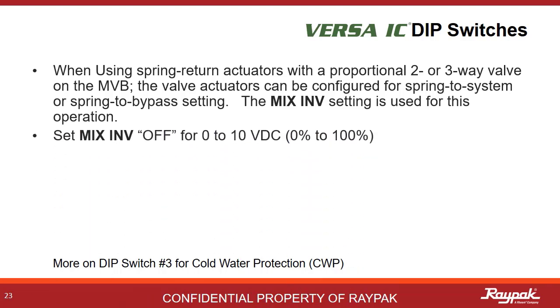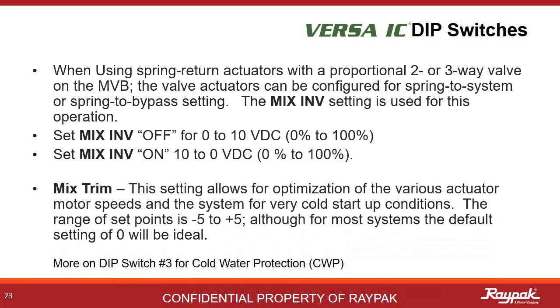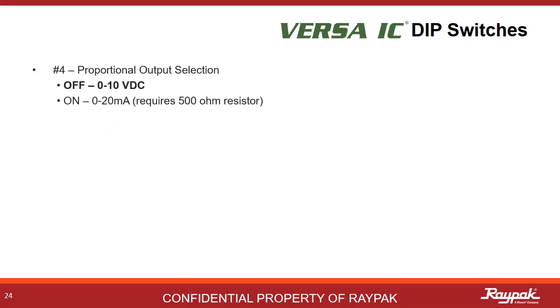If the actuator responds with a 0% to 100% open with a 0 to 10 volt DC signal, then the mix inverse is set to off. Mixed trim allows for a final fine tuning of the cold water protection system. Scaled from minus 5 to plus 5, this allows you to give the system a little nudge one way or the other if necessary.